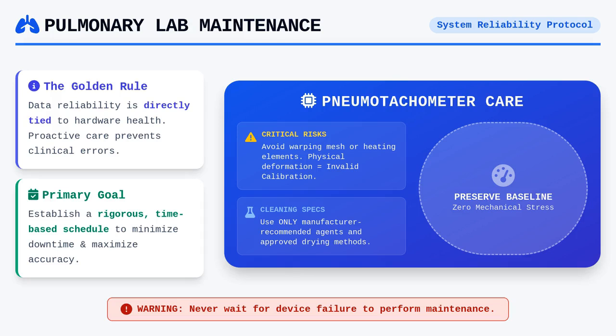This begins with the pneumotachometer, which is often the most sensitive part of a spirometry system. When cleaning these screens, you must exercise extreme caution to avoid warping the delicate mesh or heating elements. Any physical deformation of the screen changes its resistance characteristics, which directly impacts the flow-pressure relationship and invalidates your calibration constants. Always use the manufacturer-recommended cleaning agents and drying methods, ensuring that you never apply mechanical stress that could shift the calibration baseline during the maintenance routine.